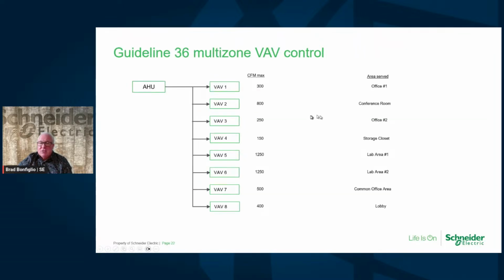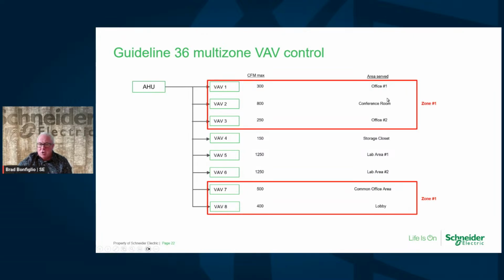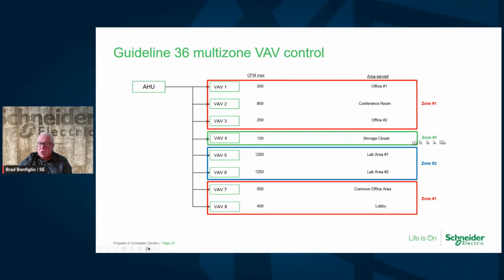And this is the way you do this with Guideline 36. You'd set up the max CFM and pick what area each one of these covers. Then we would go in and try to classify which ones are more alike each other. For example, office conference rooms would be zone 1, and common areas like the lobby we would group into zone 1 because they're very similar in nature. Then the lab areas might be zone 2, and a storage closet might be zone 3. You can see where I'm headed with this: we can put priorities on which ones are going to get the reset signal and which ones need more air the soonest. And then we put a weight to them. This is the weight factor. Remember, we talked about ignoring the ones that are not as high priority. And then the other thing we do is put in a cooling set point and a heating set point now. So we actually have two of them that we hadn't done before.